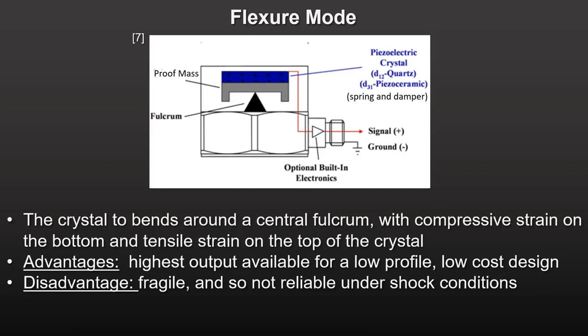In flexure mode, the crystal bends around a central fulcrum, with compressive strain on the bottom and tensile strain on the top of the crystal. You get very high sensitivity in a small, low-cost package. However, the design is fragile, especially under shock loads, and is used today only for very short sensors.